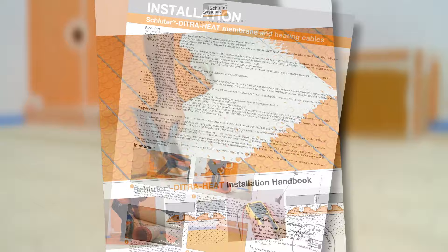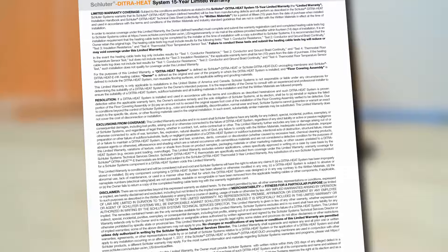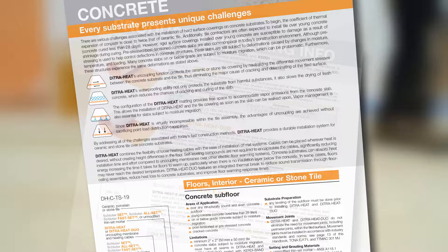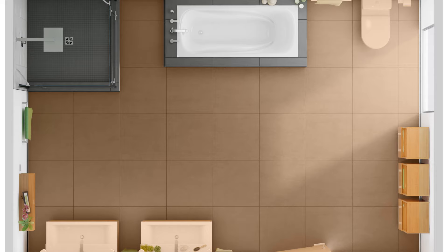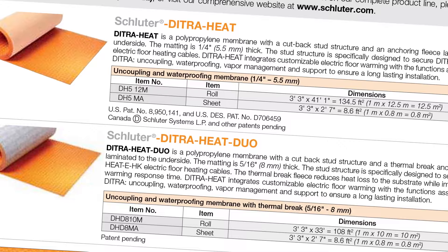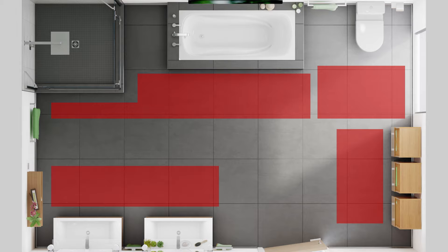The Schluter DITRA-HEAT Installation Handbook includes comprehensive installation guidelines and warranty criteria for the system. After finding the applicable detail and confirming that all requirements can be met, we start planning the required materials and quantities. Tape has been applied to the floor to mark areas where fixtures such as vanities and the toilet will be located. The DITRA-HEAT or DITRA-HEAT DUO uncoupling membrane is applied wherever tile is to be installed, typically over the entire floor. Measure the floor surface to receive tile and calculate the corresponding area. The heating cables may be installed to produce customized zones or throughout the room.